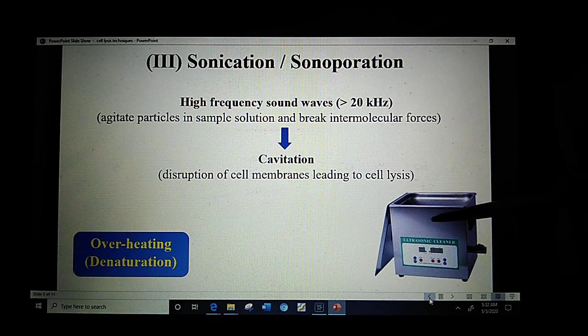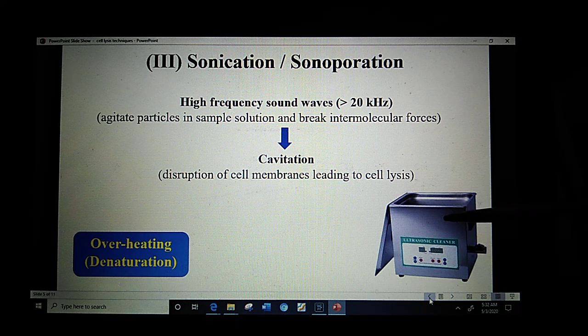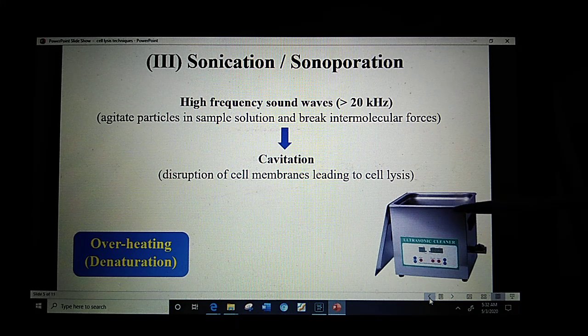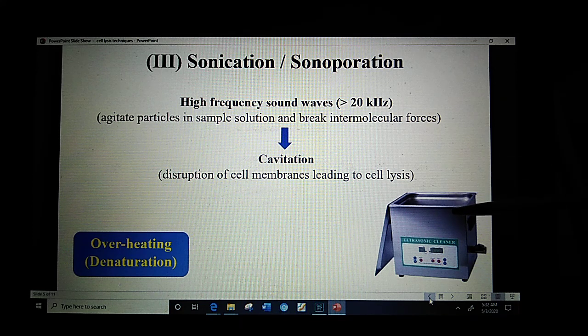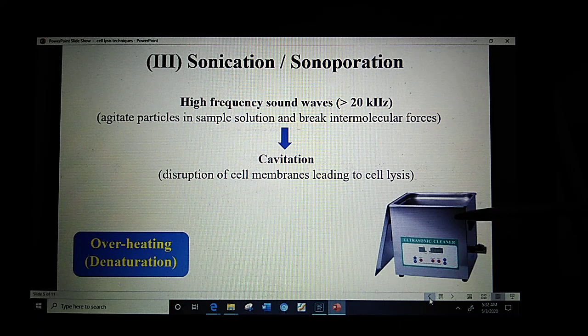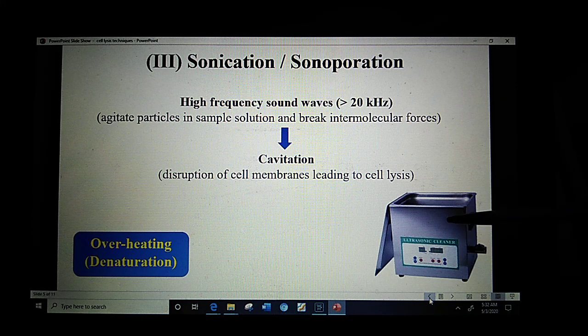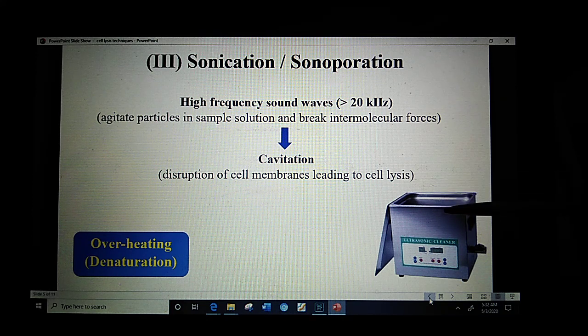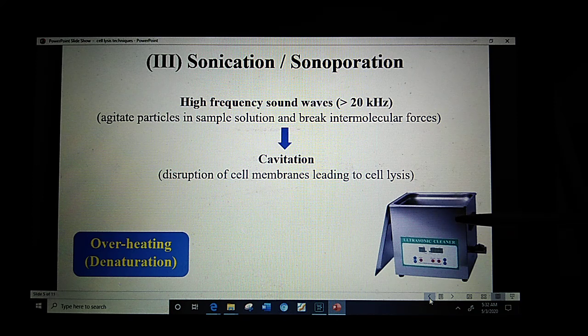The walls of the sonicator continuously produce heat due to the high frequency sound waves, which may raise the temperature of the water and lead to denaturation of the proteins. Since proteins are stable only at low temperatures, we must keep the water temperature low. For that purpose, ice can be added periodically to the water.